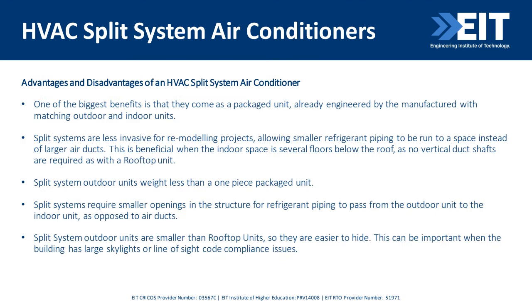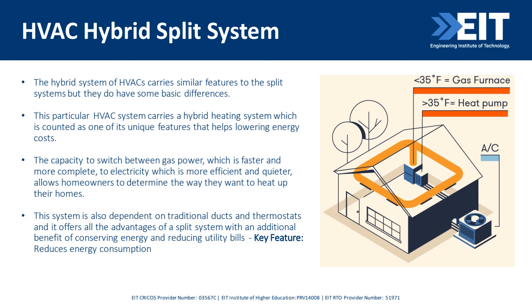Then advantages: one of the biggest benefits is it's already a package unit, so it's already engineered by the manufacturer with the matching outdoor and indoor units. It also weighs less than a one-piece package system. These split systems require smaller openings in the structure for refrigerant piping, and are smaller than rooftop units, which makes sense because the rooftop unit is one big system.